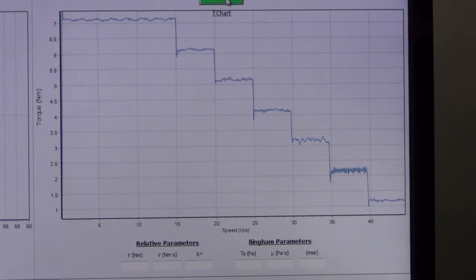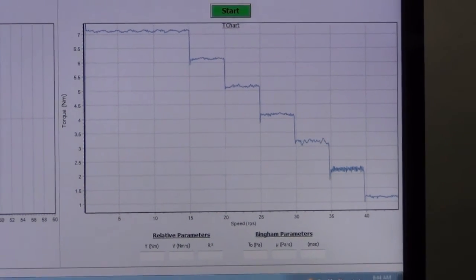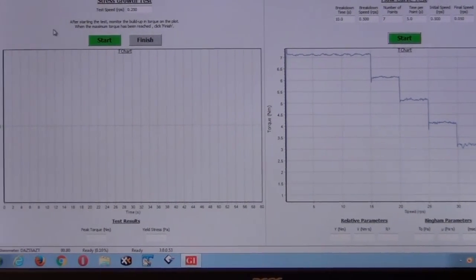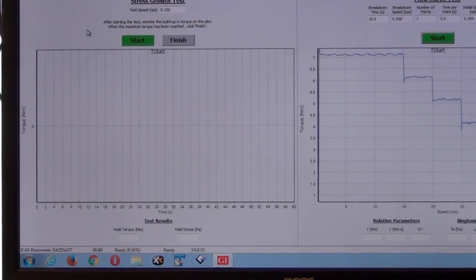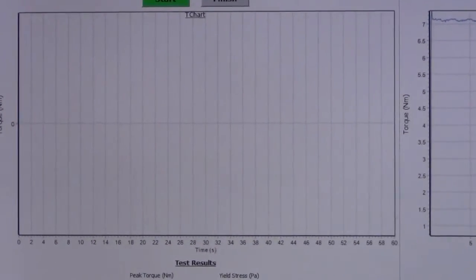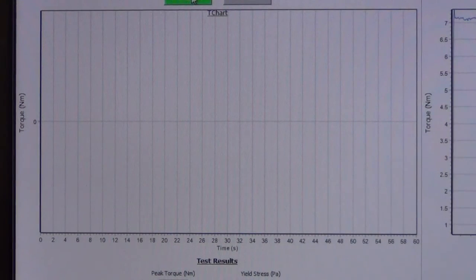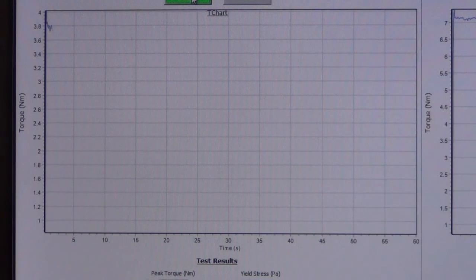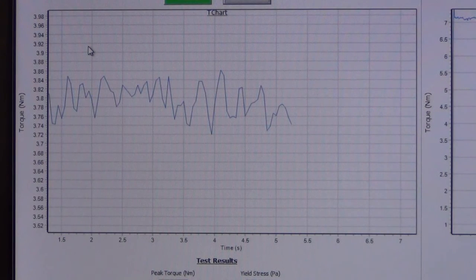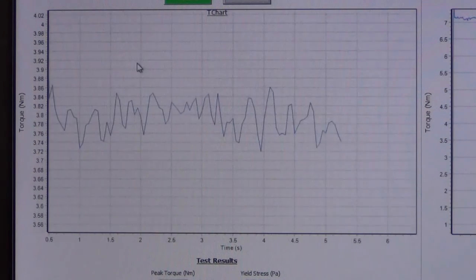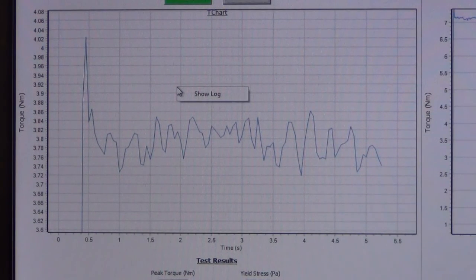Alright, now let's go take a look at the stress growth test. Now, the stress growth test, at least with this fluid, only takes a moment. I'll go ahead and let it run for 5 seconds. And then we'll zoom in and look at it. Okay, we've got our 5 seconds worth of data. Now if you click and drag from the top left to the bottom right, you basically are telling the system to zoom in. And then you right click and drag, and we can position this window where we want it.